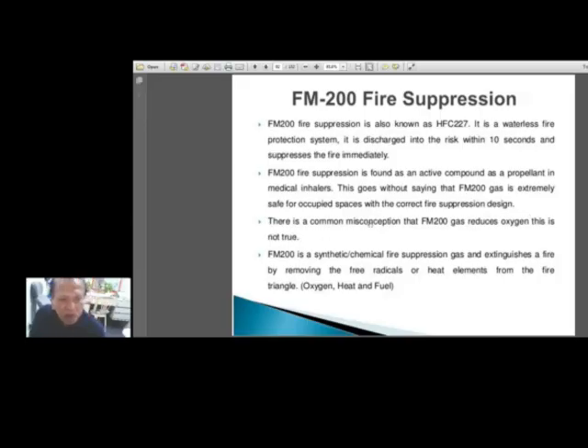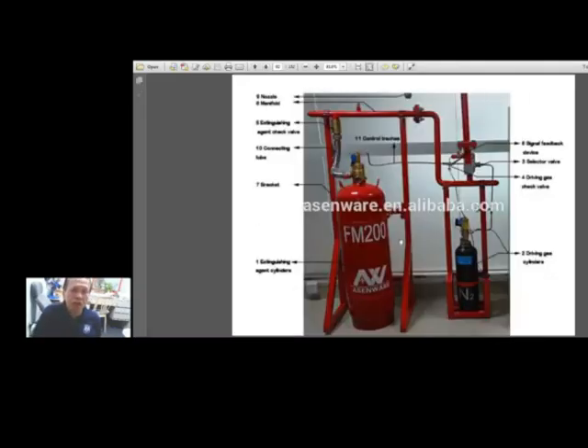There is a common misconception that FM200 gas reduces oxygen. This is not true. FM200 is a synthetic chemical fire suppression gas and extinguishes a fire by removing the free radicals or heat elements from the fire triangle. That means the oxygen, heat, and fuel. And here is a picture of how this FM200 looks like.